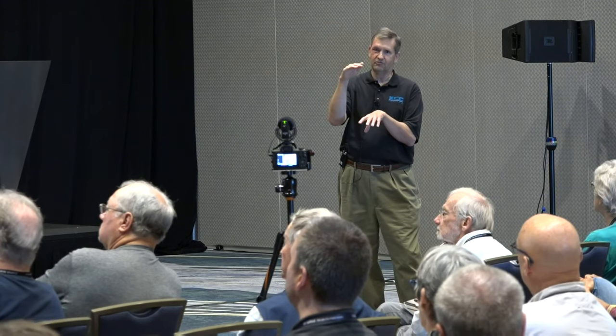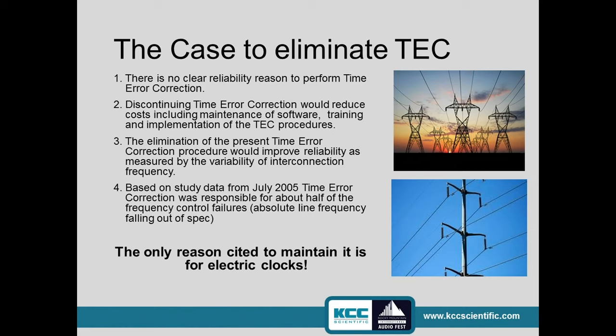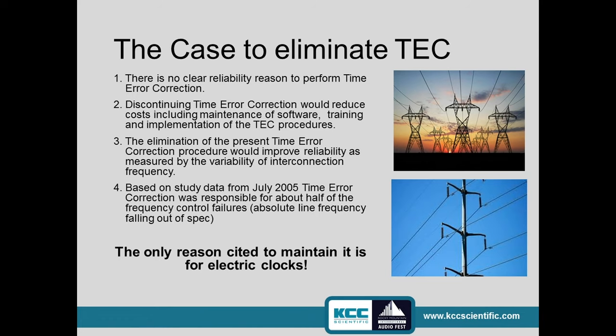Of course, getting rid of TEC would make all electric clocks lousy time keepers. So that's been stalled and pushed back, but it has been considered and we have to be aware it might actually happen. Why would you get rid of it? Because in order to make it work, generator speeds must stay within a certain range with very tight regulations — and when they go out, overreactions can lead to overcompensations and overshoots, making control harder and worse. The only reason given to maintain it is for electric clocks.